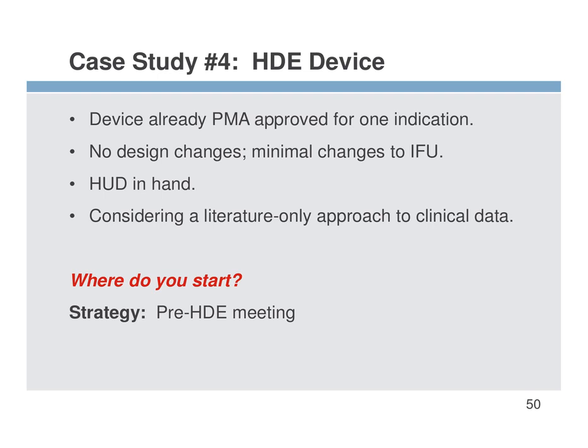Okay, so here's the follow-up question. But what if we disagree about the testing requested? So at some point, FDA is going to get tired of having a submission issue meeting and is going to tell you just submit it. And that's where you got to deal with it. You may be facing that they're not paying attention. And as a company, you're going to have to make up your mind. Do we fight this fight and go on record that we think this is good enough, or do we concede the point? And you get involved in the same sort of difficult discussions of, what's the cost of doing it over again? What's the cost of waiting 90 days to get the answer, et cetera.